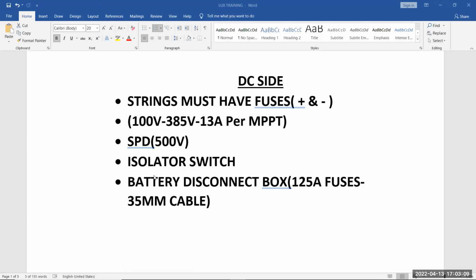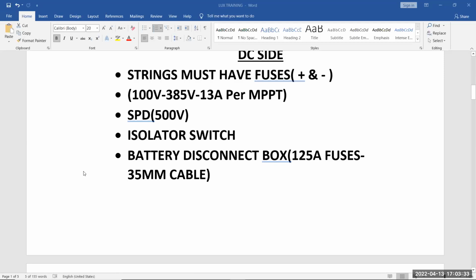Now, for your panels that are coming down, please have an isolator switch or a DC circuit breaker that's big enough for the current that you're going to run from your strings to the inverter, so that you can switch off your panels at any given time without having to loosen wires and work on live wires. This is for your own safety. If you have a system of 300 volts at, let's say, 10 amps for a 330 watt panel, you're going to have 3 kilowatts running through those wires. It's extremely dangerous to work with DC volts at 3 kilowatts of power. So please have an isolator switch installed so that you can disconnect the panels from the inverters without having to loosen a wire if you need to do something on the inverters themselves.